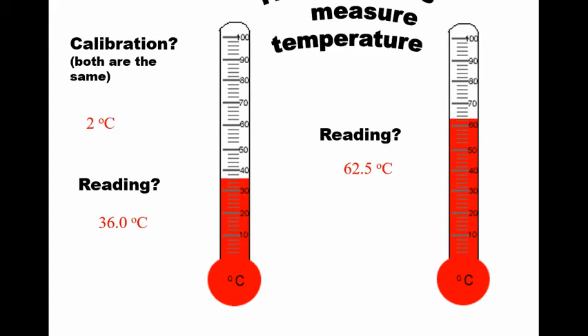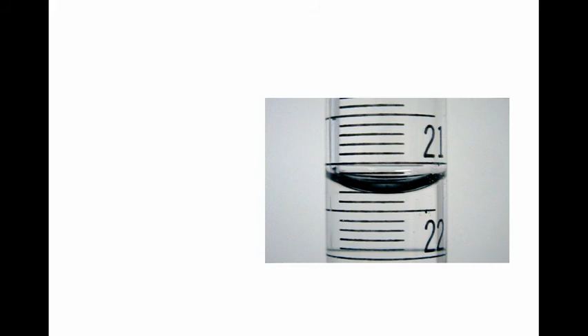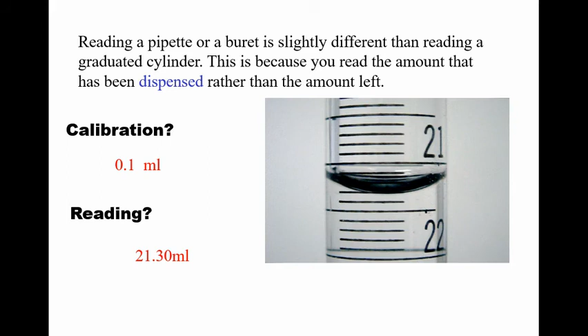Burettes are going to be measuring how much volume of a liquid is dispensed. So you're really measuring what's missing out of the burette instead of how much liquid the container holds. So in this case, notice that the 21's on top and the 22's on bottom because we're measuring how much is already gone. So my measurement better be between 21 and 22. The calibration in this case is 0.1. So I'm going to read that 21.30 is dispensed. It has to be somewhere between 21 and 22. It has 3 lines missing, so I'm going to say 21.30.